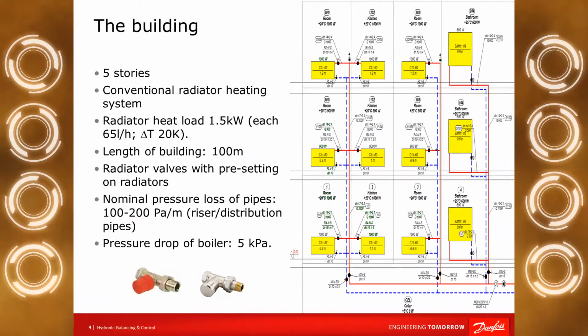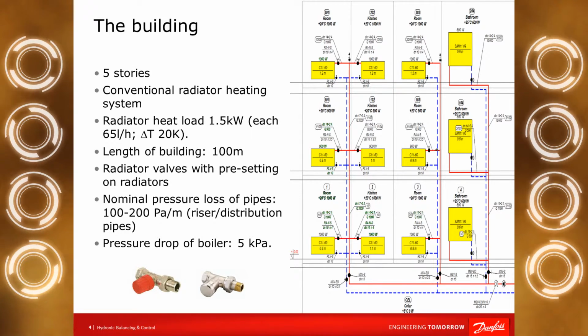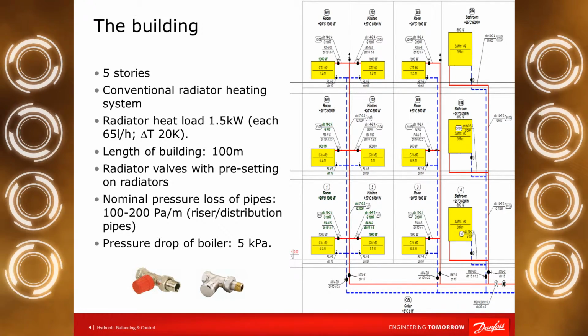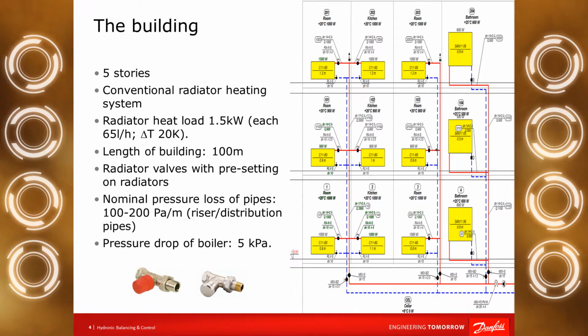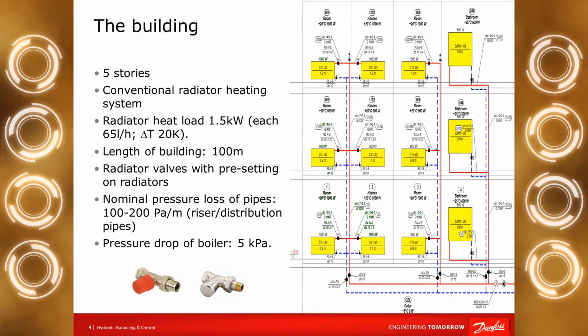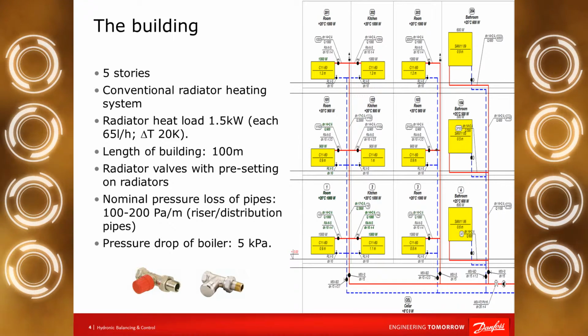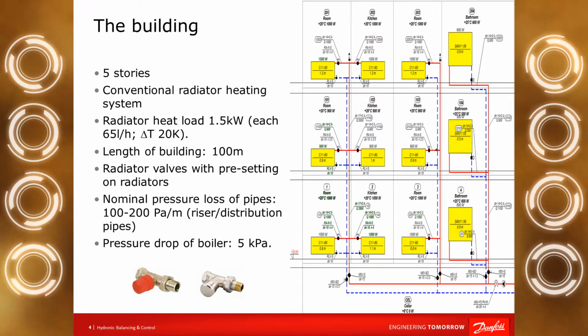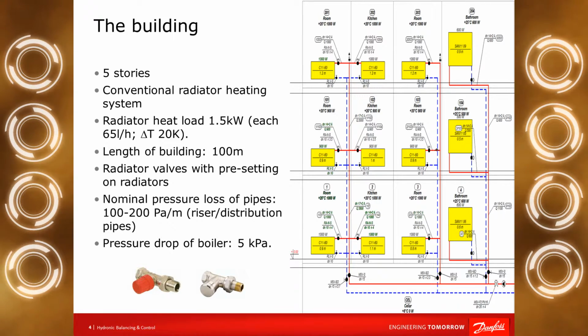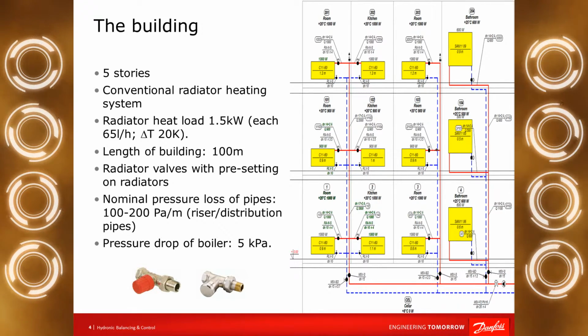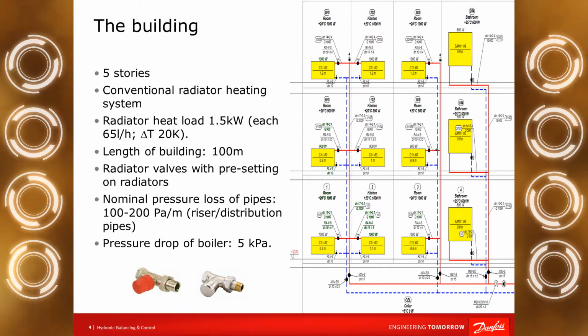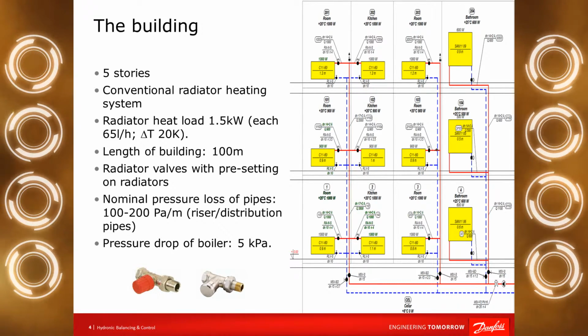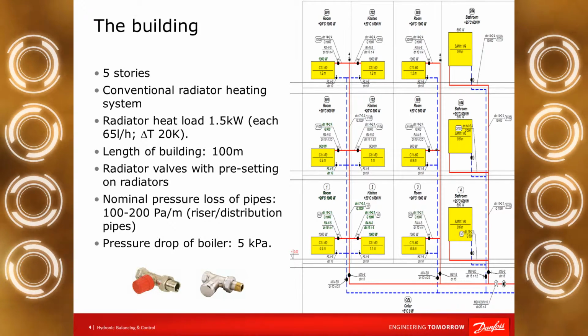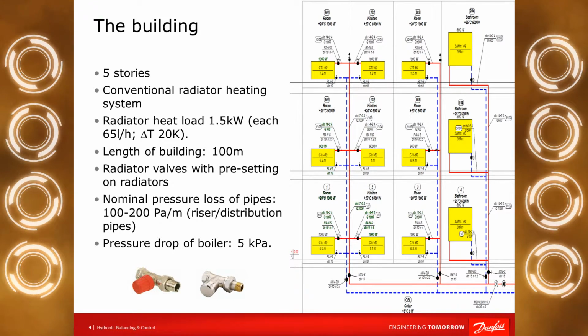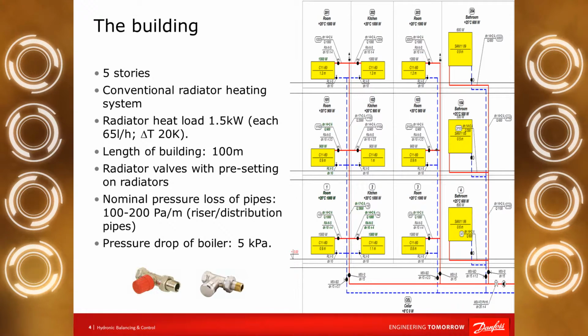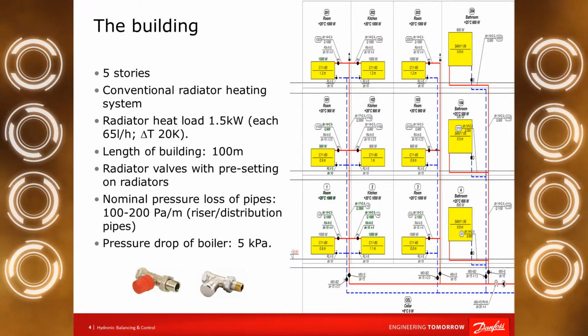I will do it using a realistic building. It could be, maybe here in Serbia, a 5-story building with a normal, conventional 2-pipe heating system with single or twin connected radiators. The average heat demand of the radiators is around 1.5 kilowatts with a 20-degree delta T. That gives a flow rate of around 65 liters per hour. This is not a very big building, around 100 meters long, and we use radiator valves and lockshield valves in the return pipe.